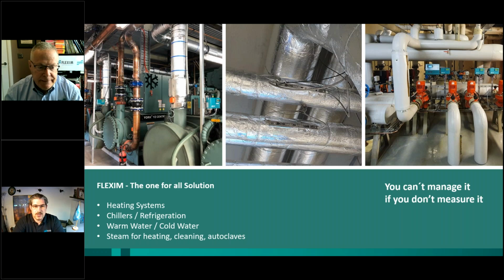So to give you some images here, how it looks in the field. On the left-hand side, this is a chiller application. This is actually from a hospital in Australia, where we have our 5 series meter installed to monitor cold water flow from the chillers. As you can see, the transducers themselves sit in a stainless steel mounting rail, which is quite slim, so easy to insulate, so you do not have any energy loss by the installation itself.